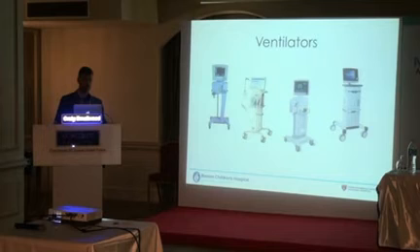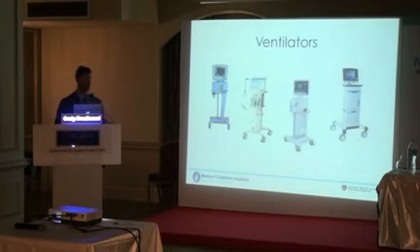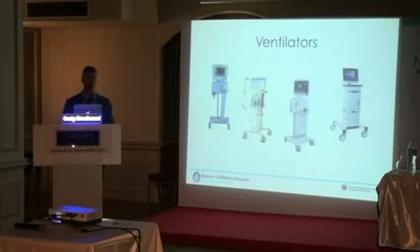The interesting thing, and the thing I've spent a lot of work recently over the last few years looking into in our neonatal and pediatric ICU, is utilizing the measurements on the mechanical ventilator. So a lot of ventilators, and these are just a handful, I know there's many more, there could probably be dozens of different devices. Many modern ventilators have either incorporated as standard or as an option a CO2 monitor. And typically, when we're talking about CO2 monitoring, we normally just care about capnography or end-tidal CO2. But a lot of these devices, these ones in particular, can measure CO2 elimination, VCO2.